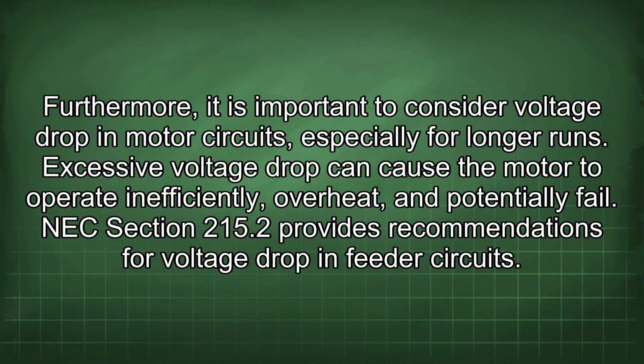Furthermore, it is important to consider voltage drop in motor circuits, especially for longer runs. Excessive voltage drop can cause the motor to operate inefficiently, overheat, and potentially fail. NEC Section 215.2 provides recommendations for voltage drop in feeder circuits.